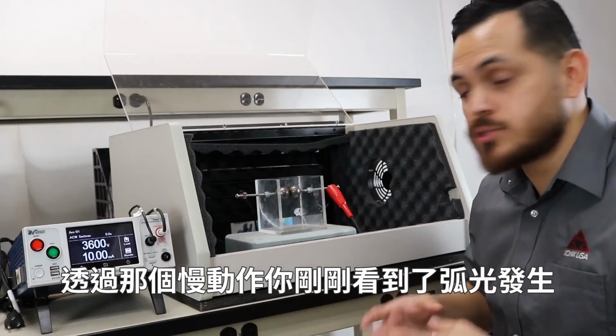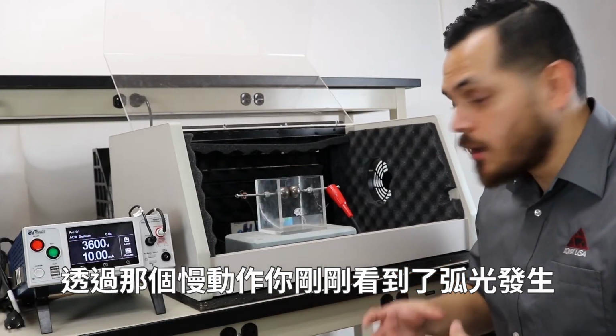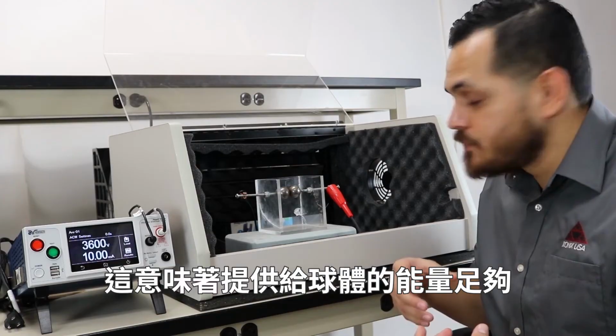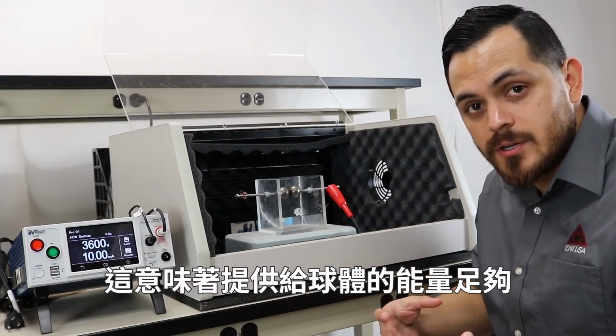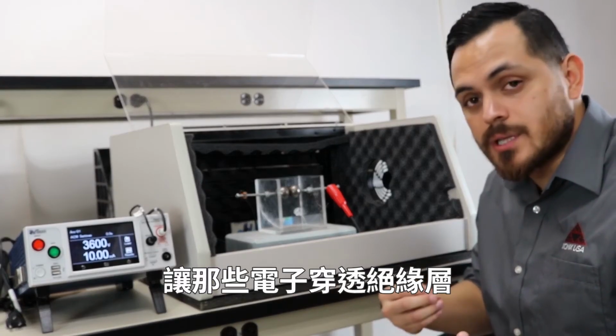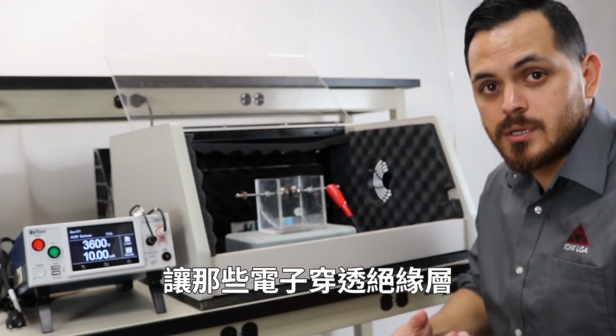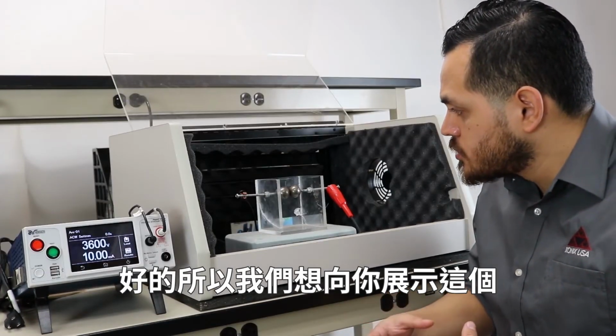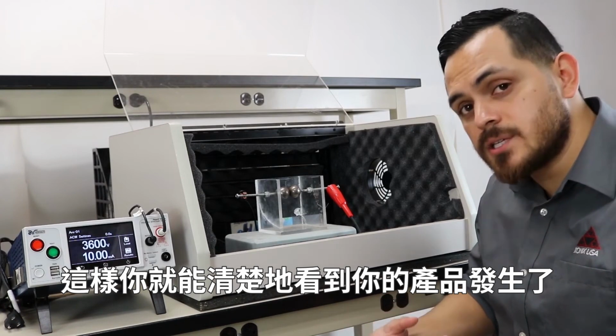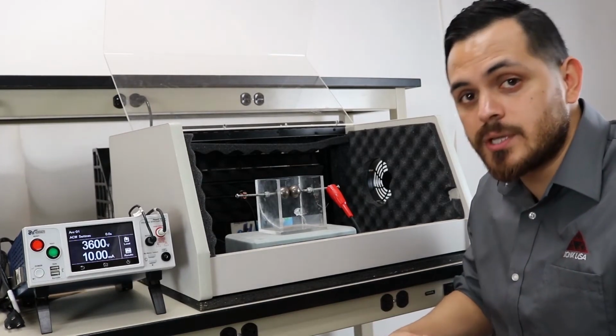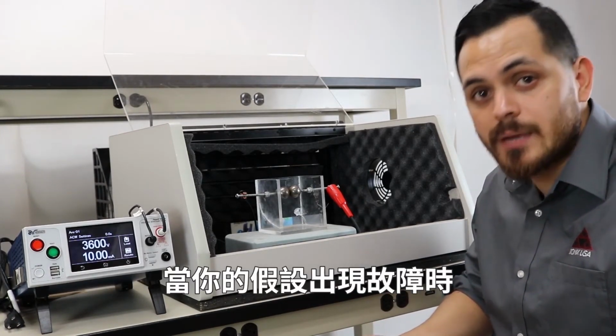So with that slow-mo, you just saw the arc happen, which meant the energy provided to the spheres was enough to let those electrons break through the insulation. Okay, so we wanted to show you that so you can get a good visualization of what's happening to your product when you get a breakdown on your Hipot test.